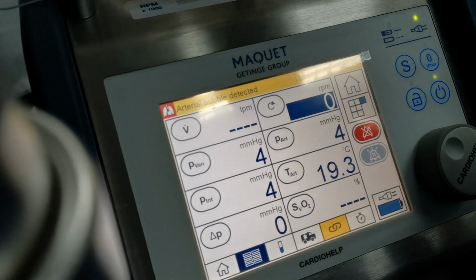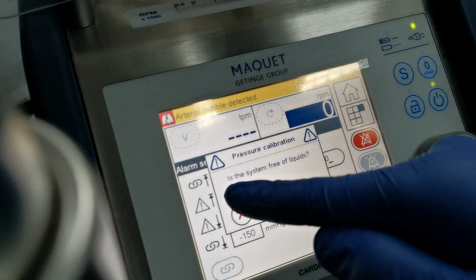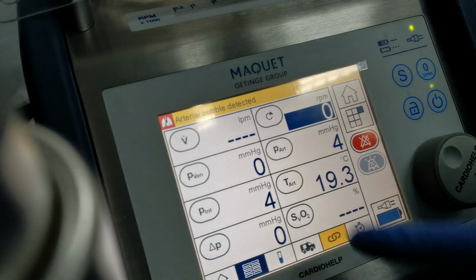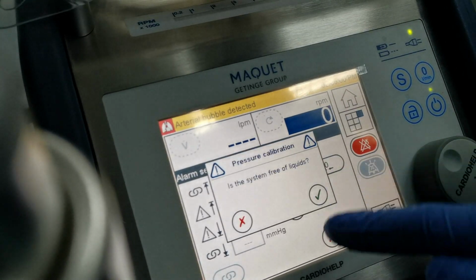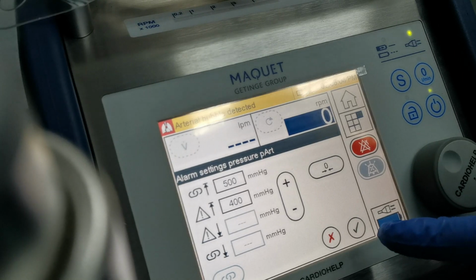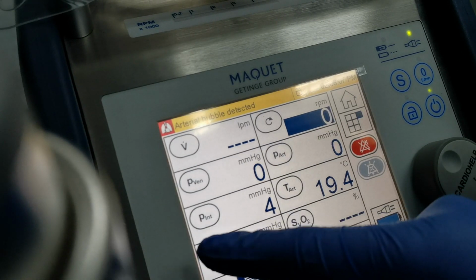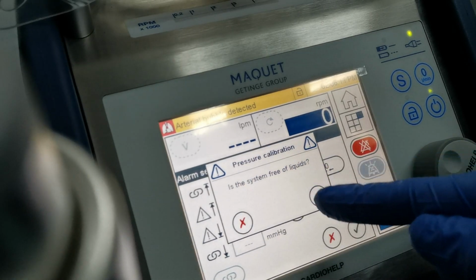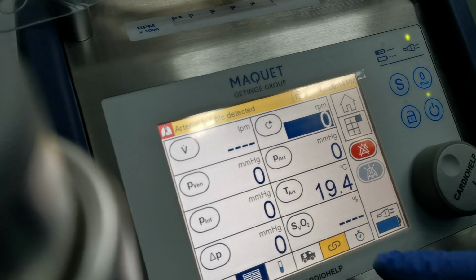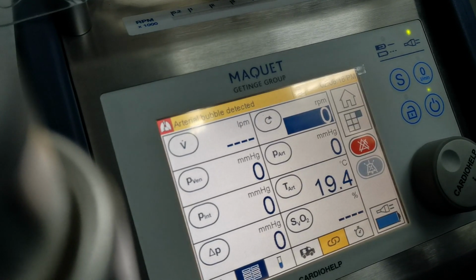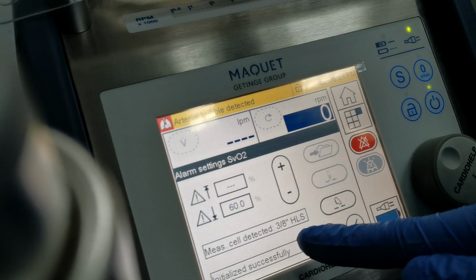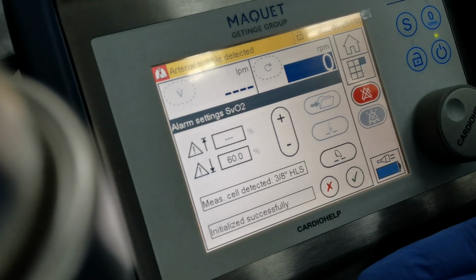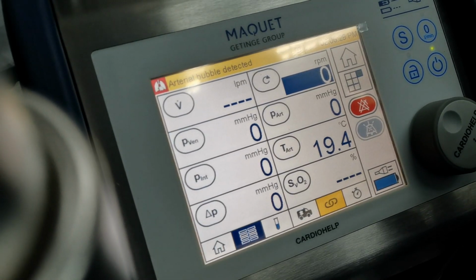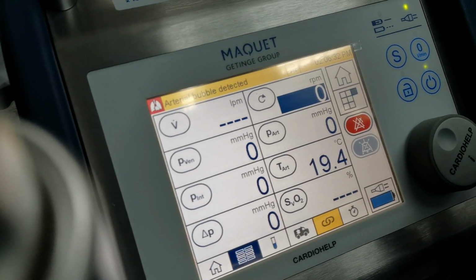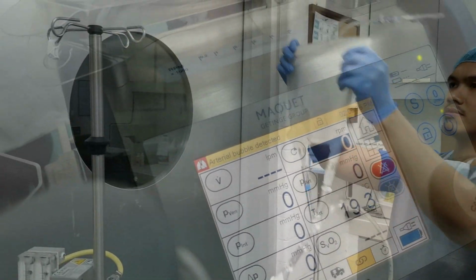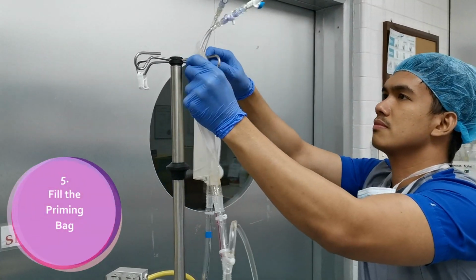After choosing the appropriate therapy, individually calibrate the integrated pressure measurements: the arterial pressure, the venous pressure, and the internal pressure. Please take note that the system must remain unprimed while calibrating the integrated pressure sensors. Therefore, calibration must be done prior to priming. Checking the venous oxygen saturation or the SVO2 on the software wall confirms that the venous probe was initialized and is identified correctly. Once the console is initialized, the circuit can now be primed with fluid.